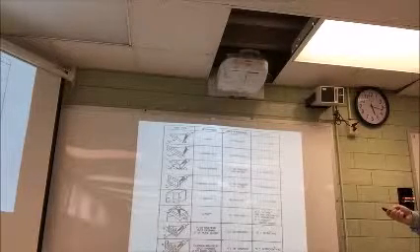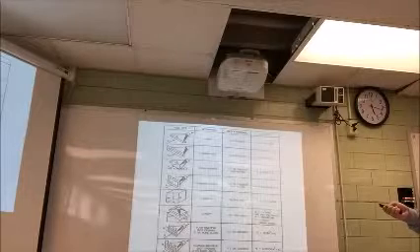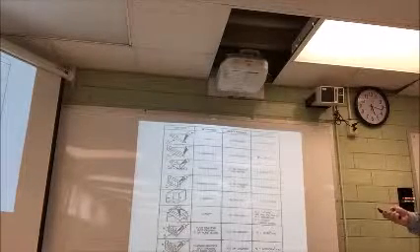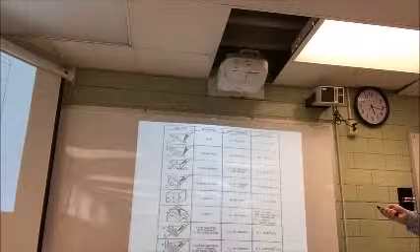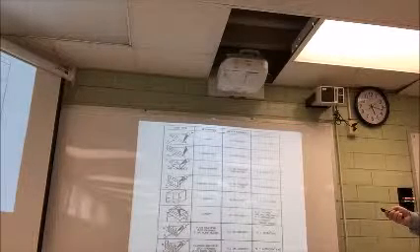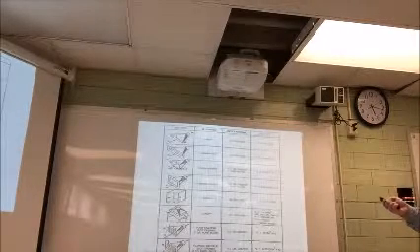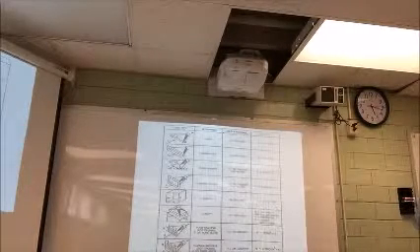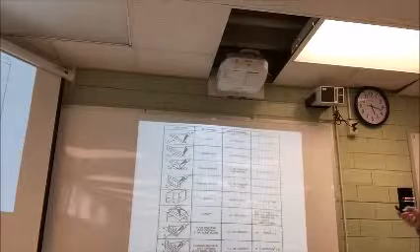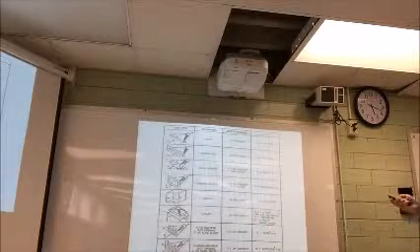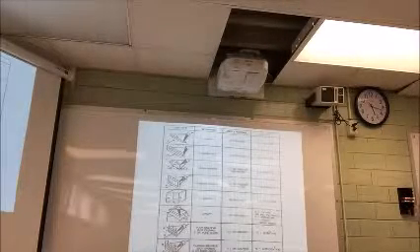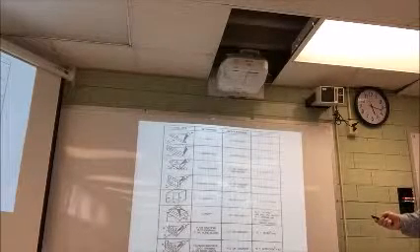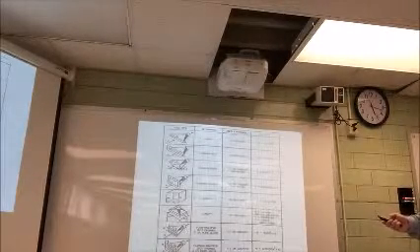Let's say I have a hood type, a slot hood, 0.2 or less. Now see this flange slot, 0.2 or less. If you look at those two, what are they talking about? Aspect ratio. Width divided by length. So my question is, if it's greater than 0.2, where do you have to go? Ding, ding, ding. Down to number 3 for a plane opening, okay?